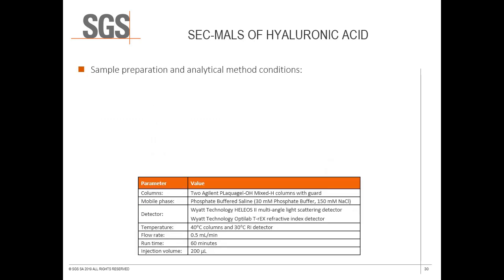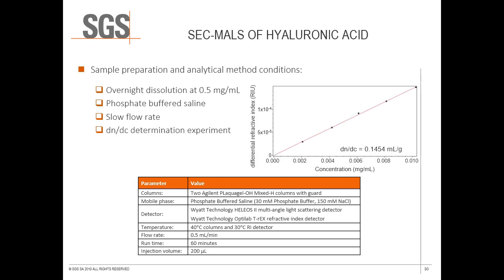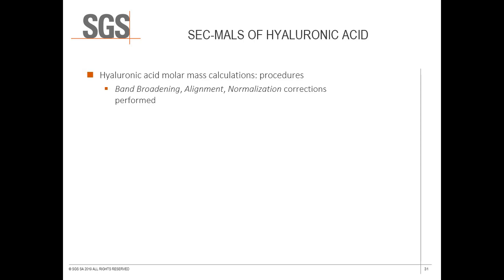The sodium hyaluronate samples submitted by the client were dissolved in phosphate buffered saline and were analyzed on the SEC-MALS system at a slow flow rate of 0.5 milliliters per minute to reduce shear forces. A separate refractive index determination experiment was performed as previously described. Band broadening, alignment, and normalization corrections were performed using a 30 kilodalton narrow polyethylene oxide standard. These corrections were applied to all samples, and the baselines and integration limits were set for each sample chromatogram.